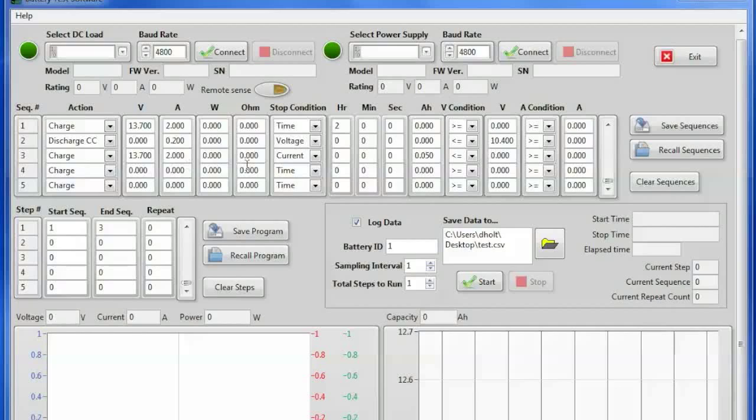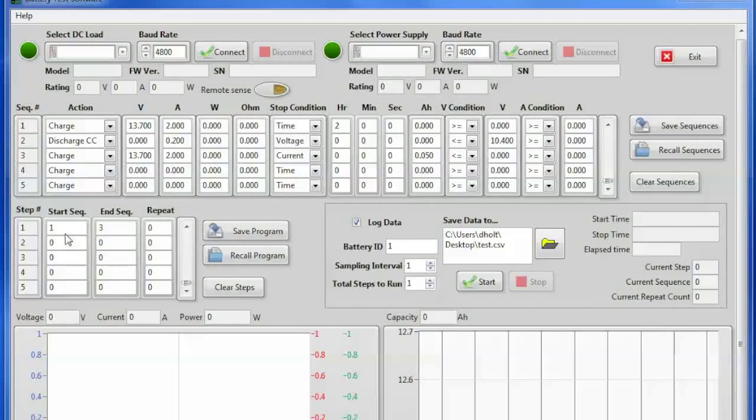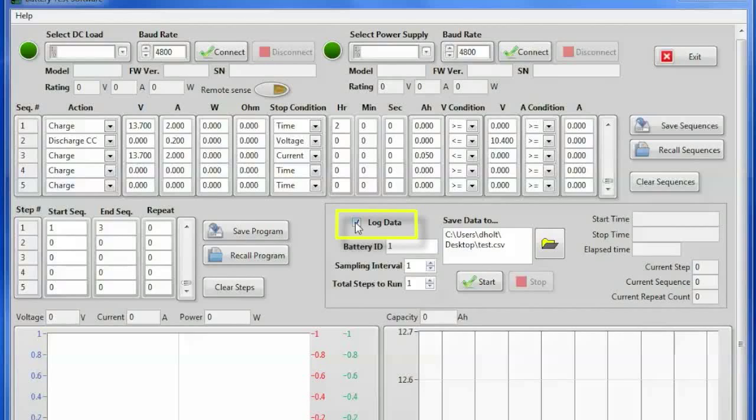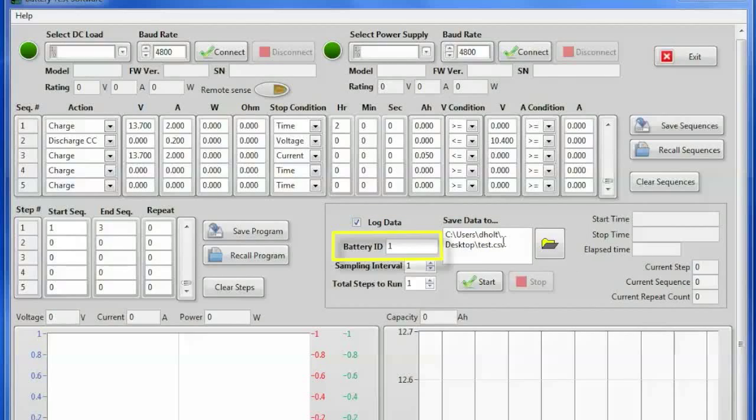So I've already pre-populated that. I've gone through now and set those sequences. Down here you see now I have to say once my sequences are done I'm going to start with a sequence 1 and end with 3. So it's going to start with 1 and 3 up there. Do a charge, discharge, and charge again. If I wanted I could repeat the test but for this we're just going to have it not repeat. And I've saved it. I want to log the data so I've selected this and told it where to save the file. Over here you've got a battery ID. You might have a certain number or a serial number or internal lot number for your batteries. For our purposes I just put it as a 1. So this information will be on the report when it's done. So you've got a battery report for a specific battery.